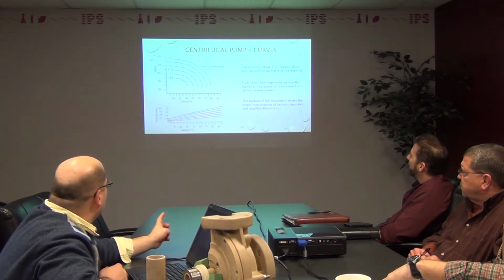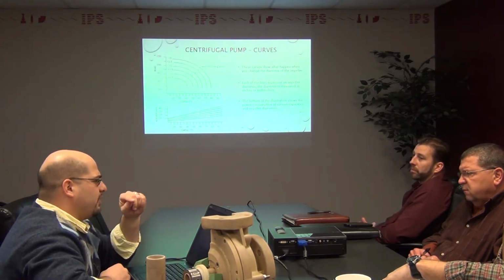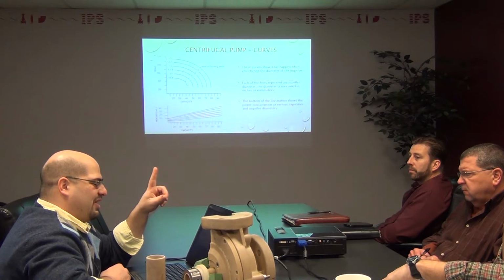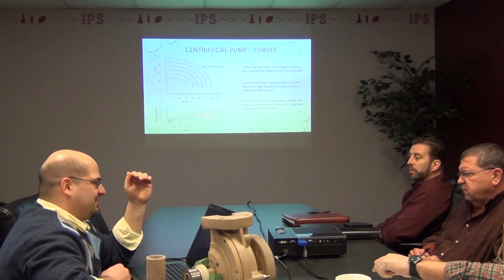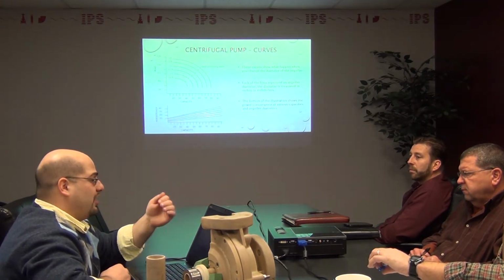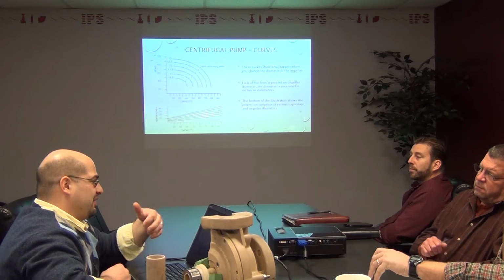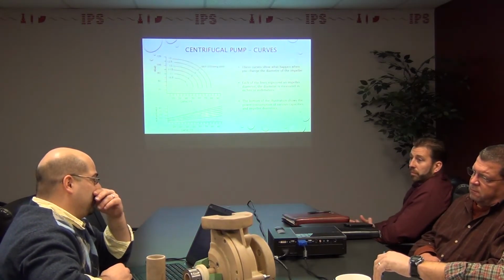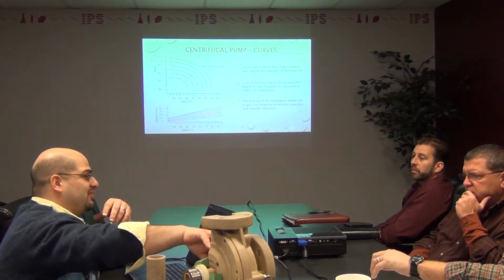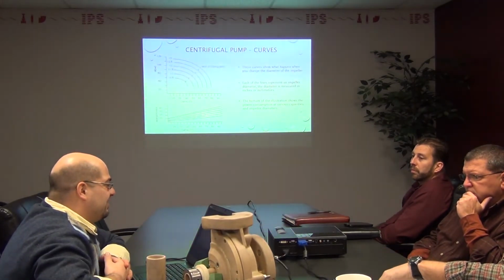Well, any other questions on that? I'm glad that you asked that question because it is one point that I want to bring up: this is the only condition in which you would overload a motor, or have a higher amp draw on a motor, for a centrifugal pump. All your other known failure modes are under load, you have a low amp draw. If I'm cavitating, and cavitating is pulling air bubbles into the pump, or I have entrained air, or other issues, it reduces the amount of flow that gets through the impeller, and it reduces my overall horsepower. So you see that on the flip side.